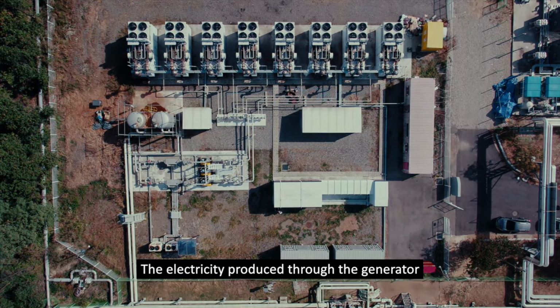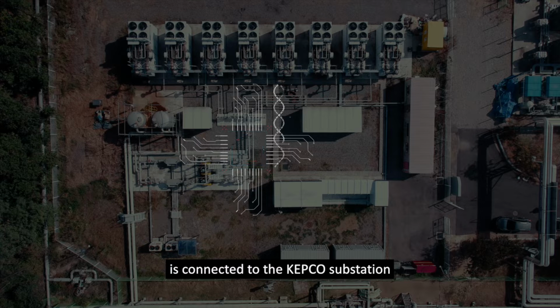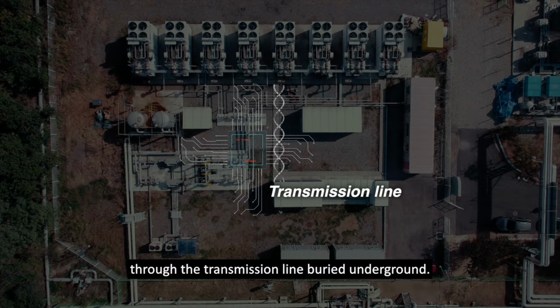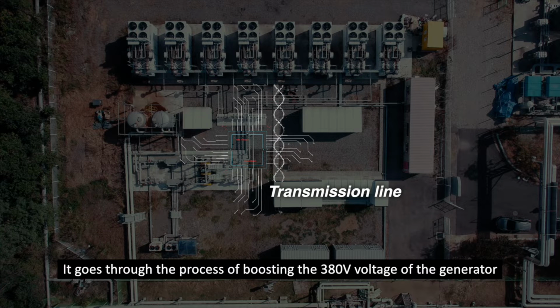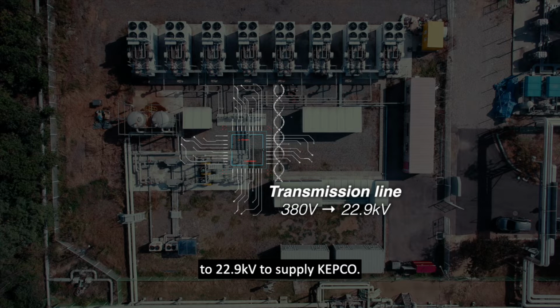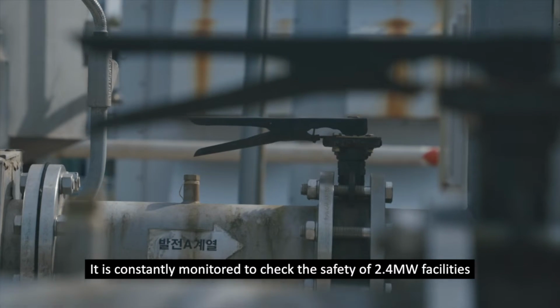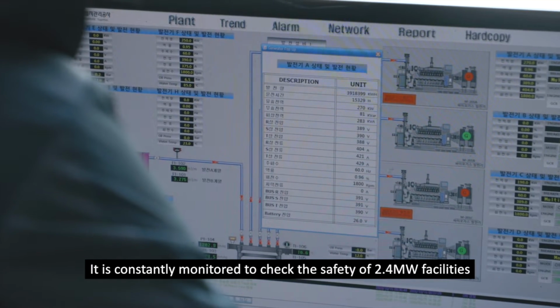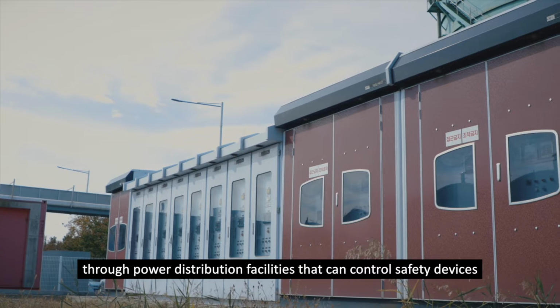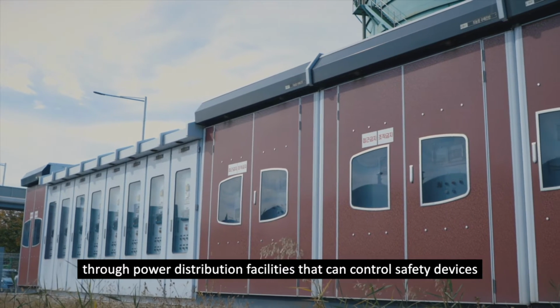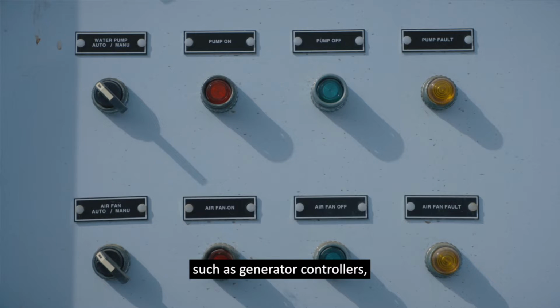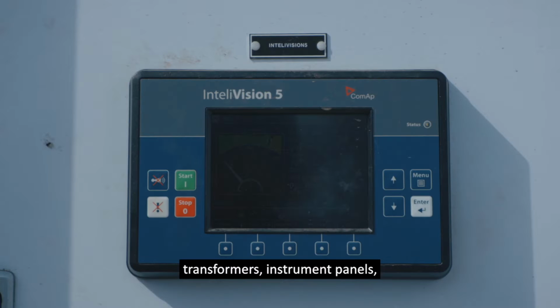The electricity produced through the generator is connected to the KEPCO substation through the transmission line buried underground. It goes through the process of boosting the 380 volts of the generator to the 22.9 kilovolts to supply KEPCO. It is constantly monitored to check the safety of 2.4 megawatt facilities through the power distribution facilities that can control safety devices such as generator controllers, transformers, instrument panels, and circuit breakers.